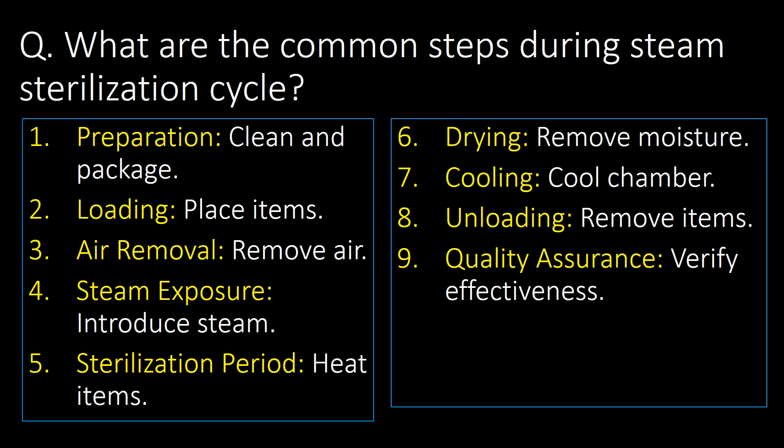The fourth step is steam exposure — here we introduce steam inside the chamber. The fifth step is the sterilization period — in this step, the actual sterilization happens. The sixth step is drying — here we remove moisture. The seventh step is cooling — here we cool the chamber.